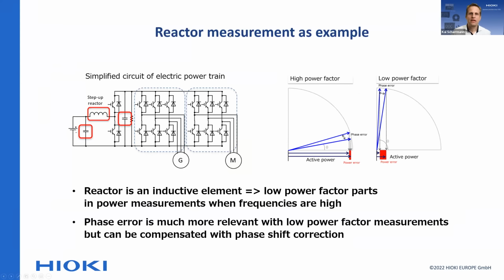And now let's have a little bit of a look at a reactor measurement as an example. And again, why is this so important? A reactor is an inductive element, and we're using the same graphic on the top left as we did before. It's a simplified circuit of an electric powertrain. And you see this big step-up reactor, you see this second, smaller step-up reactor with the high frequencies. And if you want to measure that reactor, which is an inductive element, you always deal with low power factor parts in this power measurement, especially when the frequencies are high.